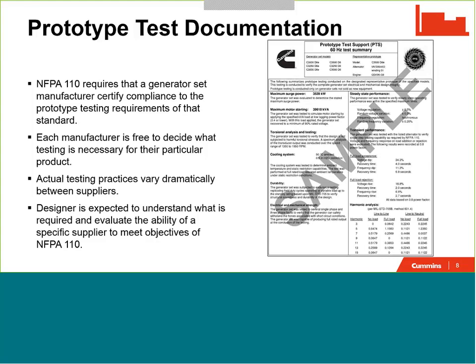And what you're looking at here on the right-hand side is an example of a document that some generator set manufacturers do provide, that provides a high-level overview of the prototype testing that has been conducted on a particular unit or a particular configuration of a product. This can be very helpful when trying to understand the prototype testing that has been conducted on a product, and I always recommend that you request this type of document or something similar to it in your submittals. This should be a requirement from a generator set manufacturer.